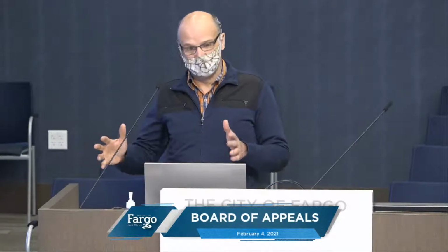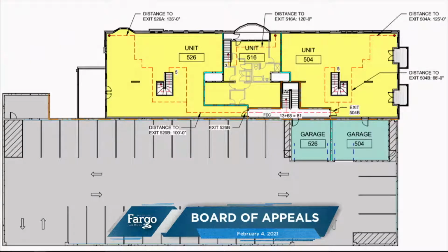Careful consideration was made for what the ventilation requirements are on opposite ends of the building. Our parking garages are placed within the building, but even if they were pushed all the way to an exterior wall, they would not impact the openings required on any level of the parking garage. So we're not in any way affecting the open parking garage with this construction.